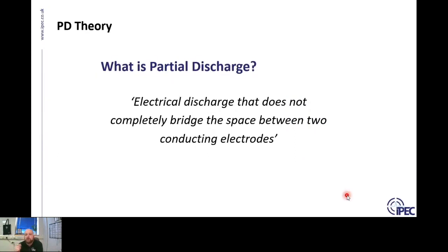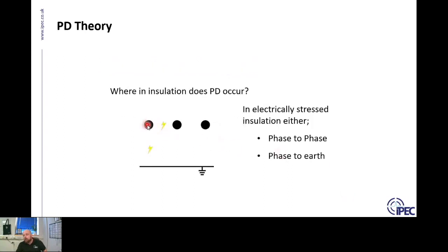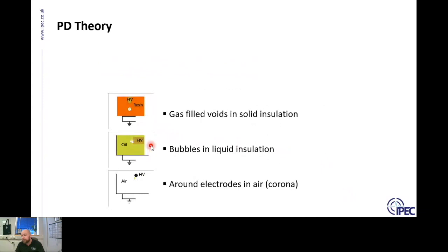The PD is occurring very specifically at a localized point of a defect — where there may be a flaw. It can occur from the core to earth, between cores, or between phases. Basically, anywhere the insulation may be compromised or have a defect. In solid insulation it can occur in a gas-filled void — maybe a manufacturing defect or a small gas-filled void not completely sealed during a joint or termination.